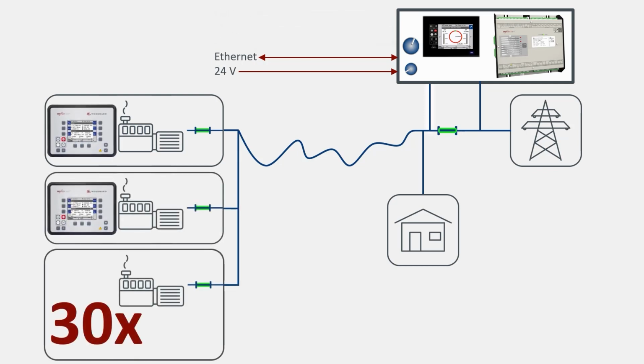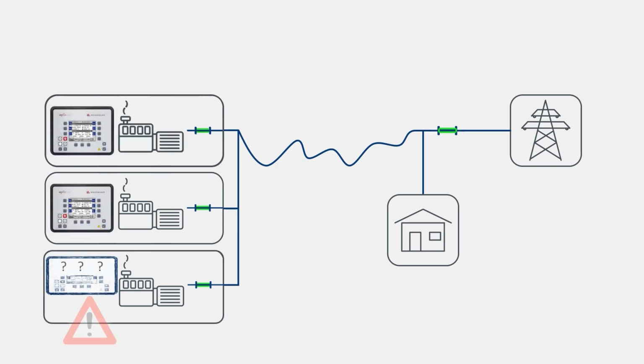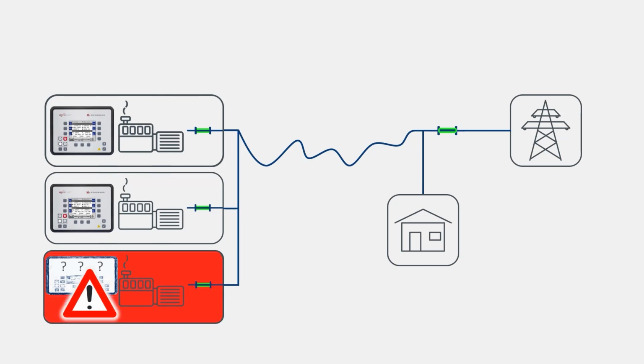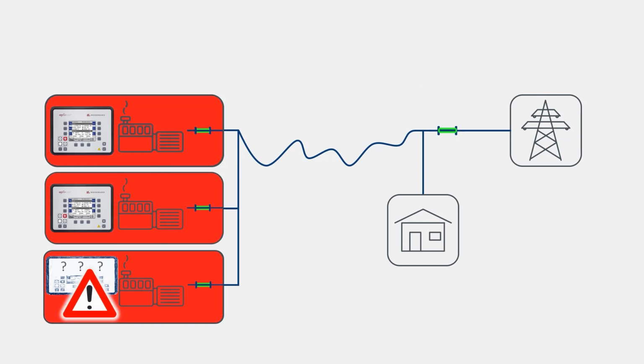EasyGen controllers can operate a generator fleet of up to 32 generators in parallel. It is easily possible to parallel different engine brands and sizes. However, using generators with different controller brands comes with drastic technical limitations and works only via the droop mode or analog load share lines. Therefore, it is highly recommendable to standardize on one generator control brand.